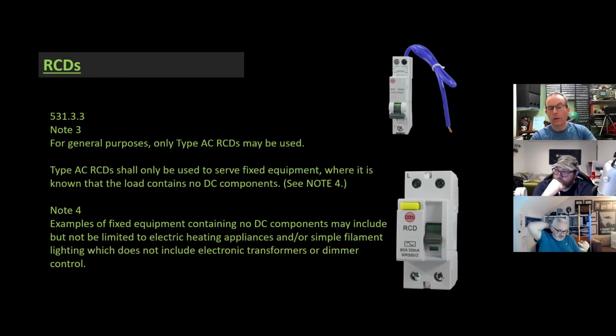So we could potentially be connecting loads without knowing it, and manufacturers need to give us more transparency. The Schneider manual talks about a maximum 10 milliamp leakage from cookers, which completely defeats the 9 milliamp maximum limit on circuits.